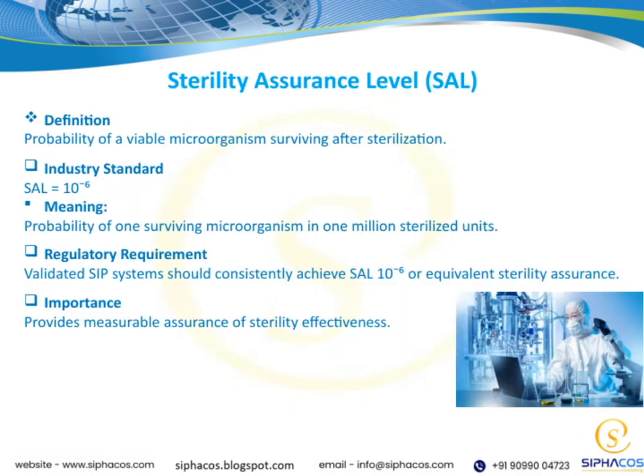Let's talk about sterility assurance level, or SAL. It's a way to measure how likely it is that a single microorganism survives after sterilization. The industry standard is set at 1 in a million. That's SAL 10 to the minus 6. In other words, out of a million sterilized units, only one might still have a living microbe. Regulatory bodies require validated sterilization systems to consistently meet this level. This gives us a clear, measurable assurance that sterilization is truly effective.